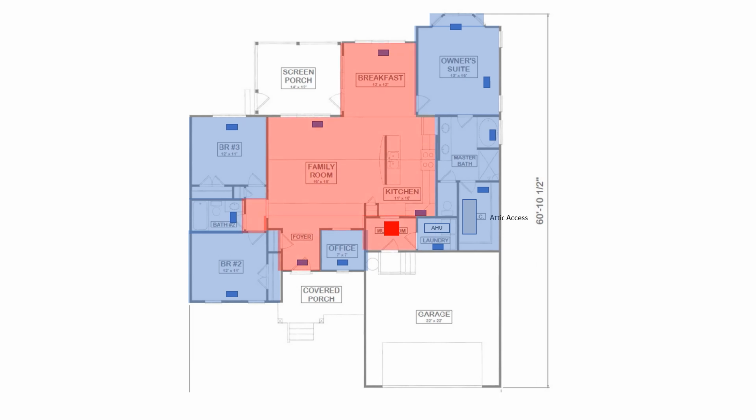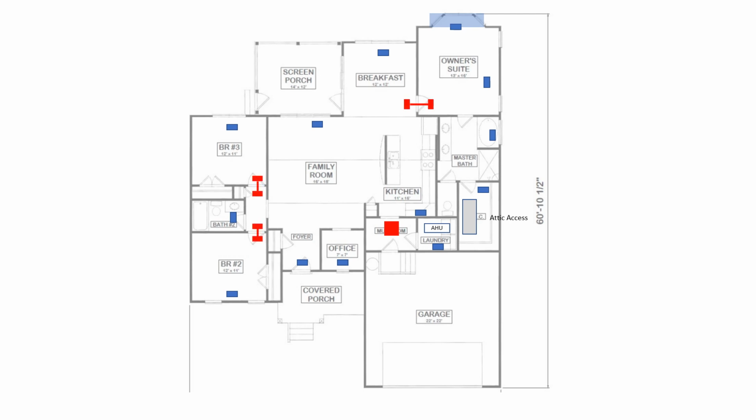An even worse problem is the main area in the house, which has all of the return, but not nearly enough supplies. The exact opposite will happen. The main area will depressurize and start leaking hot, humid, dirty air uncontrolled into the space. And this is why a lot of houses are uncomfortable, because these room pressure imbalances drive bad air into the house. So what is the solution?